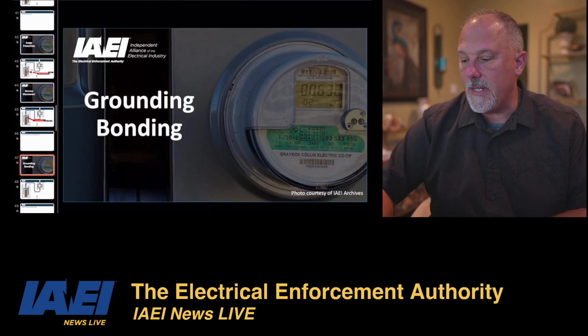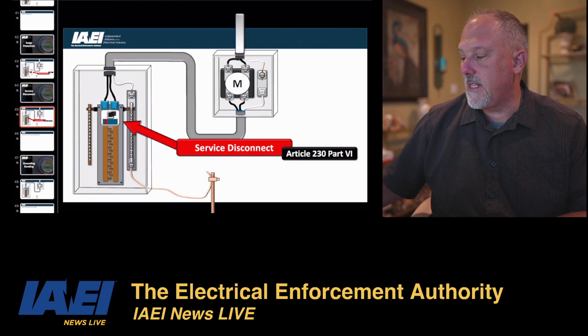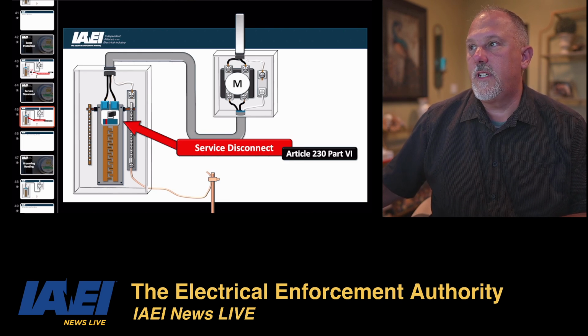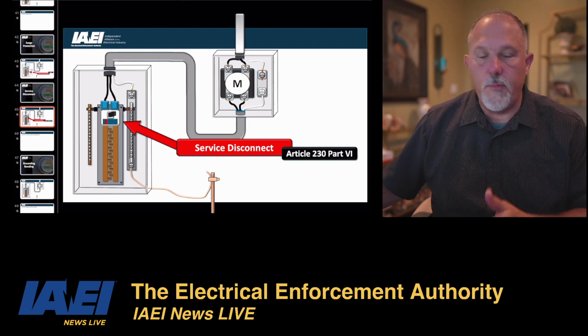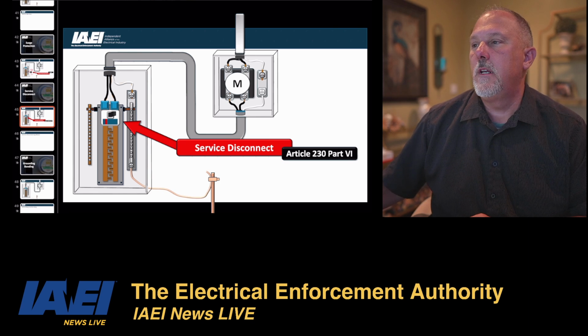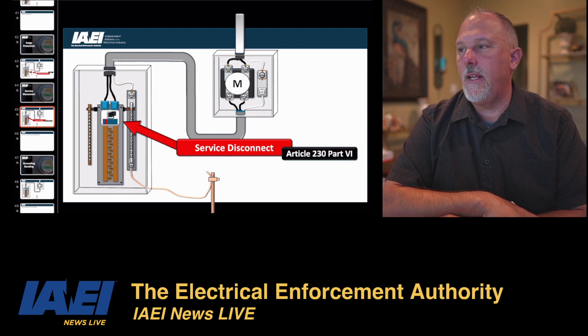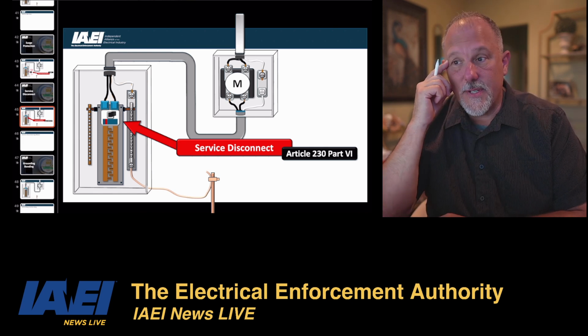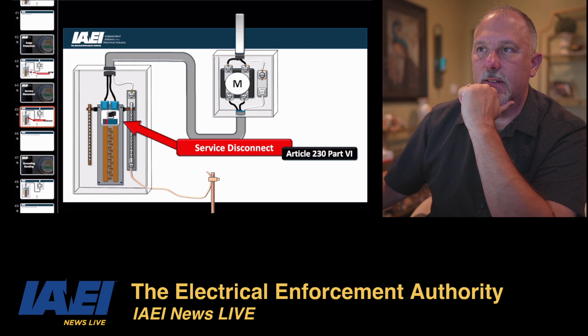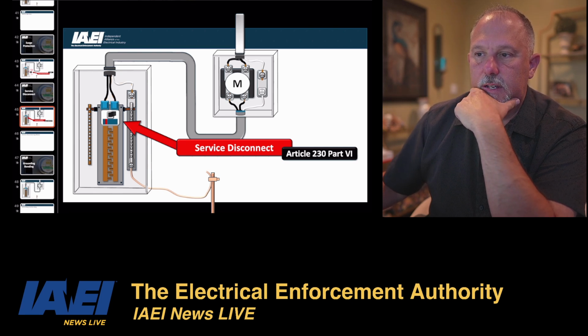We talked about grounding and bonding. Talked about the service disconnect, which is Article 230, Part 6. Your disconnecting means shall be provided to disconnect all ungrounded conductors. Service disconnecting means shall be installed in a readily accessible location. Don't put them in a bathroom. You can use remote control, but make sure you follow the rules. You have to permanently mark it as a service disconnect, and it has to be any equipment that is suitable for use or suitable only for use. So this was, I'll tell you, this was my dilemma. Where is it? Anyway, yeah, service equipment.